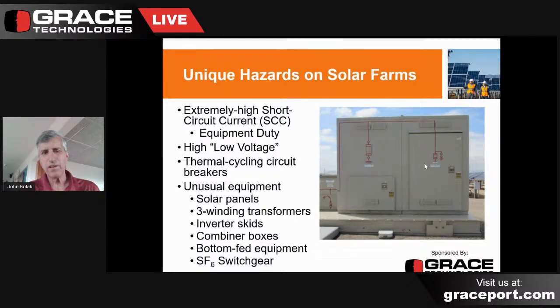Well, of course, now the wind and solar farms have come into play. Our low voltage system, so to speak, or the low voltage side of a transformer, for example, may be much higher than 600 volts. Solar farms, the wind farms now are running at 1500 volts. And they're still low voltage systems. They're configured in the manner of a low voltage piece of equipment. So therefore, things like lockout, tagout, and all that on low voltage systems that are still more than 600 volts, we're still going to use low voltage techniques to do that. So why this is important, for example, is you may have a piece of equipment that runs at, say, 860 volts, and even though it's more than 600 volts, you're going to follow low voltage procedures. In other words, you wouldn't, for example, put on personal protective grounds. You wouldn't be required to do protective grounding on low voltage systems that are configured like that. So it's kind of an important point, and I imagine someday we'll change the codes to agree with that.